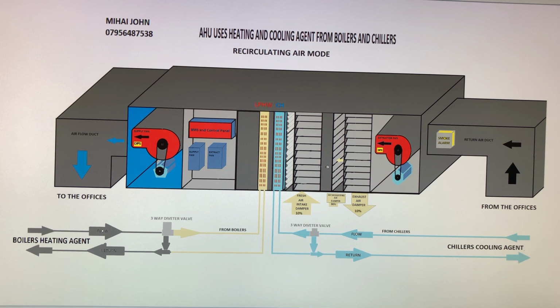After ensuring the damper positions are as I described to you earlier, the building management control will call the boilers to run. Let's assume there are many AHUs and the boilers are already running. They can be woken up by this BMS control, but if I have many AHUs, each AHU can wake up the boilers because they work independently, and the boilers provide heating agent to all the AHUs in the building, not only to one. Then this AHU, if it doesn't need too much heat, will only redirect the heating agent back into the return. You will have a three-way diverter valve.